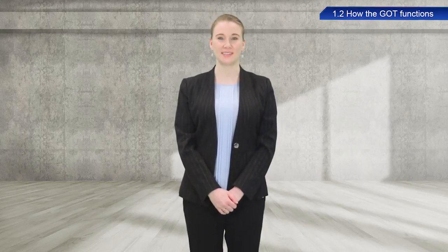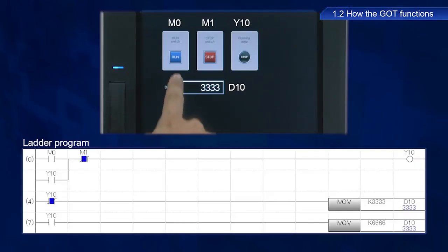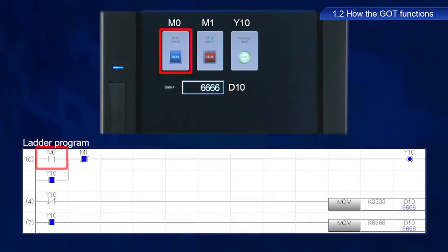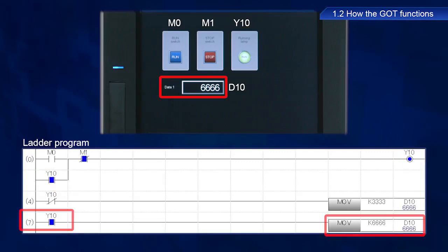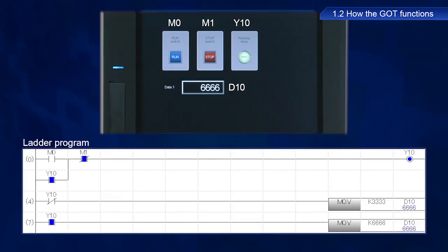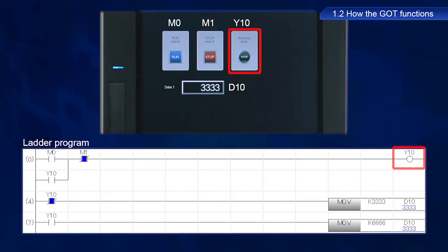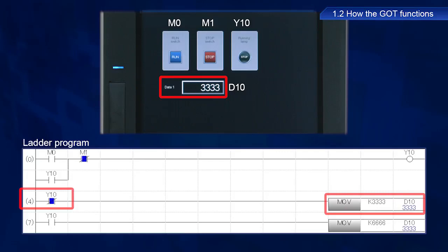Let's take a look at a PLC ladder program. Pressing the run switch triggers an input of M0, which causes the running lamp Y10 to turn on. Y10 is a self-retaining circuit, so the lamp stays on. The input of Y10 triggers a move transfer command to display a value of 6,666 in D10 for data1. Pressing the stop switch triggers an input of M1, which turns off Y10 via a normally closed contact. A value of 3,333 appears in D10 via the Y10 normally closed contact.